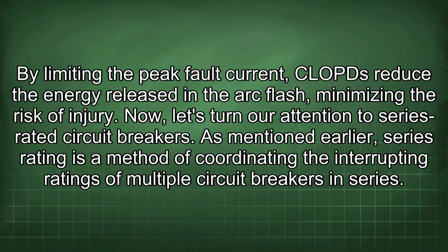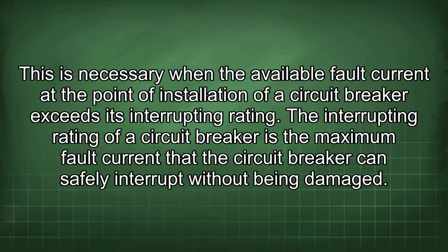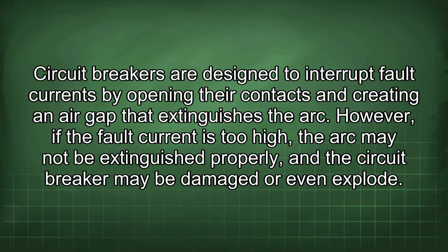As mentioned earlier, series rating is a method of coordinating the interrupting ratings of multiple circuit breakers in series. This is necessary when the available fault current at the point of installation of a circuit breaker exceeds its interrupting rating. The interrupting rating of a circuit breaker is the maximum fault current the circuit breaker can safely interrupt without being damaged. Circuit breakers are designed to interrupt fault currents by opening their contacts and creating an air gap that extinguishes the arc. However, if the fault current is too high, the arc may not be extinguished properly, and the circuit breaker may be damaged or even explode.